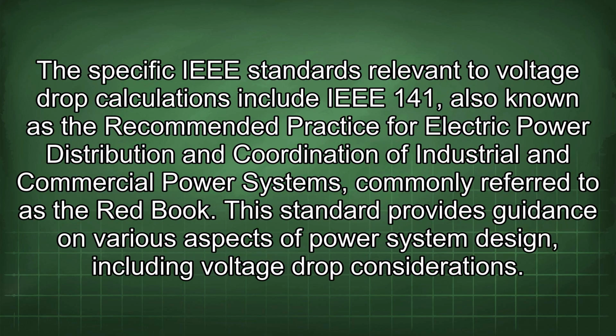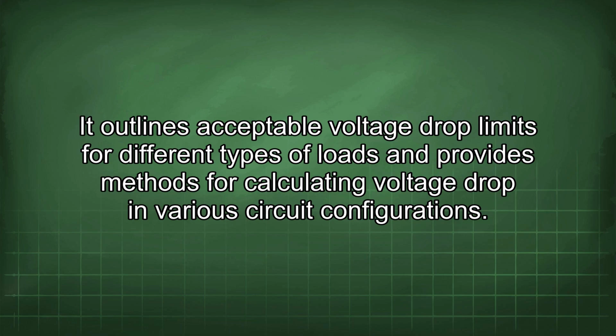The specific IEEE standards relevant to voltage drop calculations include IEEE 141, also known as the Recommended Practice for Electric Power Distribution and Coordination of Industrial and Commercial Power Systems, commonly referred to as the Red Book. This standard provides guidance on various aspects of power system design, including voltage drop considerations. It outlines acceptable voltage drop limits for different types of loads and provides methods for calculating voltage drop in various circuit configurations.